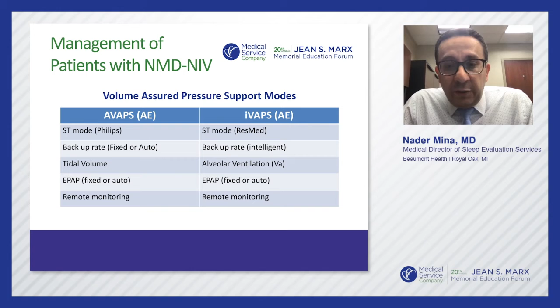They can also function in several modes. Both of them have backup rate. In AVAPS, it could be fixed or auto. In IVAPS, it's called intelligent backup rate. In AVAPS, you control the tidal volume, or you set a target tidal volume, versus on the IVAPS, you set alveolar ventilation or VA volume. In both machines, you can use either fixed EPAP or auto EPAP, and both devices offer remote monitoring.